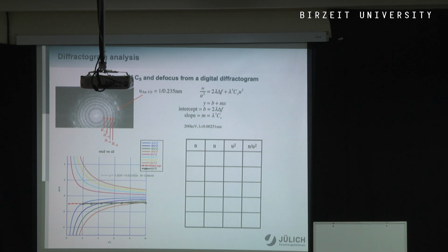You get very large error bars, which not only depend on how these positions are measured, but also on whether they are on a sloping background. And this also explains why automated routines are now required for measuring aberration coefficients in practice.